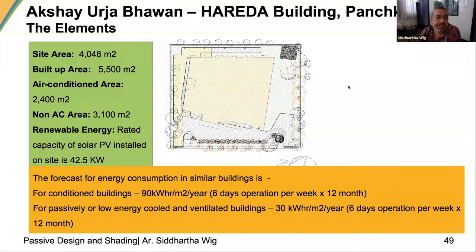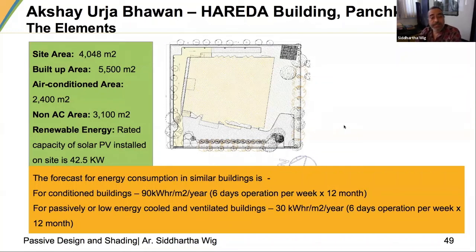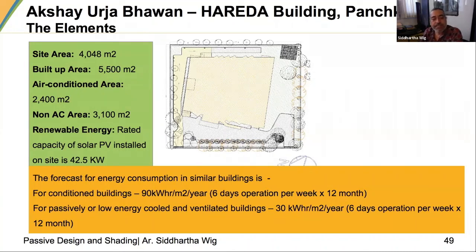It was a national competition with a very interesting brief: the building should not be connected to the electricity grid or water grid at all — the idea was a net-zero building for both water and energy. We started by benchmarking the expected energy consumption: for a conditioned building it was about 90 kWh per square meter per year; for passive low-energy buildings it was about 30 kWh per square meter per year. This was our basic benchmark.